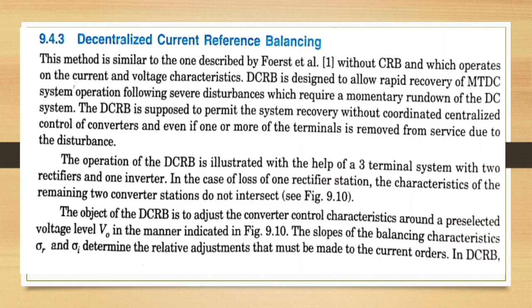Operation of the DCRB is illustrated with the help of a 3-terminal system with 2 rectifiers and 1 inverter. In case of loss of one rectifier station, the characteristics of the remaining 2 converter stations do not intersect. The object of the DCRB is to adjust the converter control characteristics around a pre-selected voltage level V0 in the manner indicated in the figure.